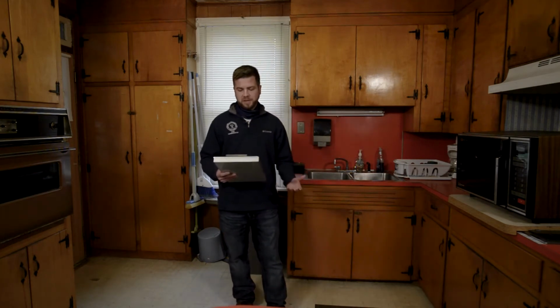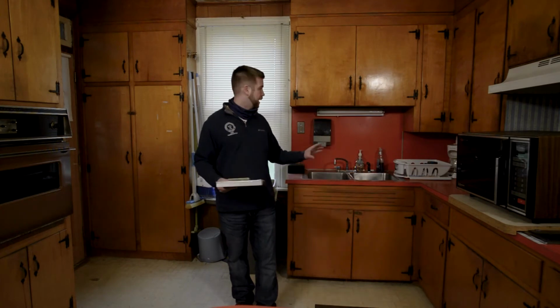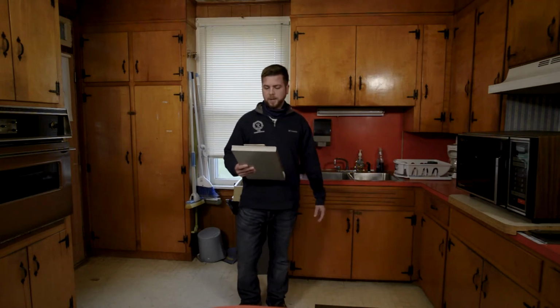And as Sean mentioned last week, as this is true in every room, we want to make sure there's no outlets above any electric baseboard heaters, and if so, those outlets will need to be moved. And we're also checking any receptacles that are within a 6-foot sphere of the kitchen sink. They have to be GFCI protected.